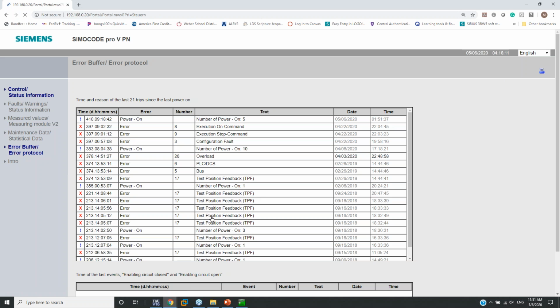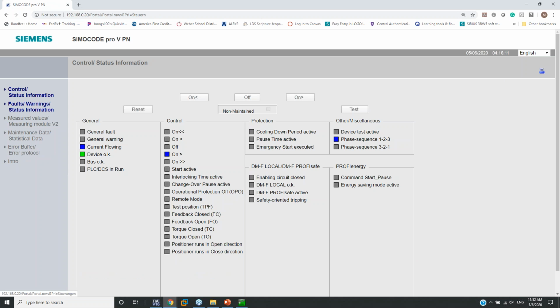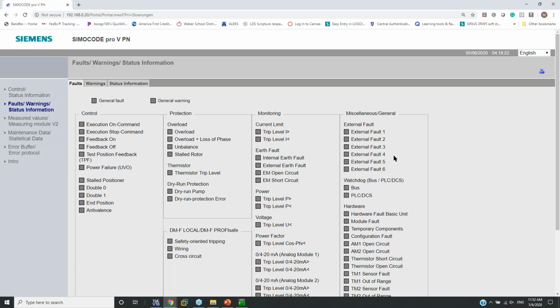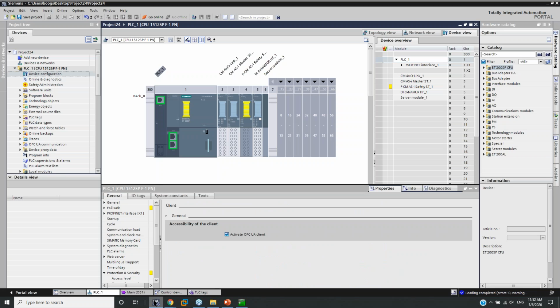All right. Now let's go back to faults and warnings. And this is my last thing that I'll show you and we'll call it a day. Did you guys know that your little web page publishes these external faults? Let's say that I did put in an RTD card and I had it on a pump housing, monitoring the temperature of a pillow block bearing. Well, how do I communicate to the operator that that's what's giving the fault? Well, it comes as external fault. Well, okay, what is it? Unless you have this Orphan Annie decoder ring to tell you what that means, they have no idea. Well, let's go in.